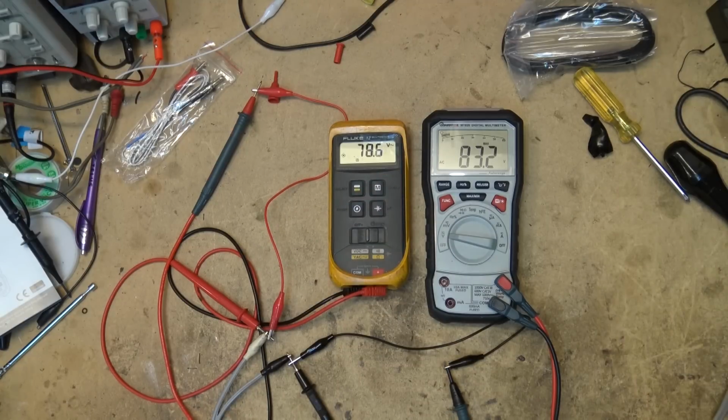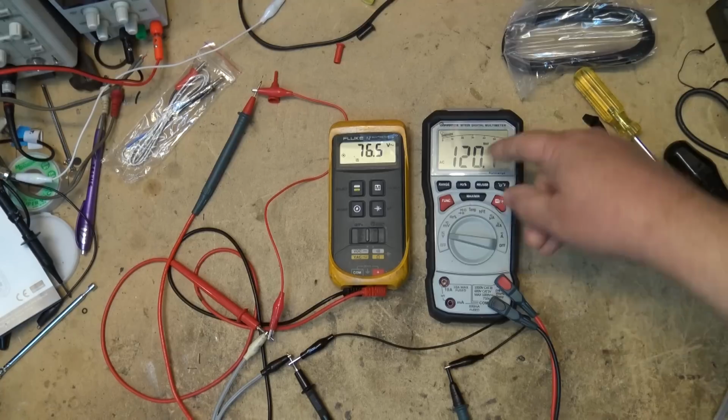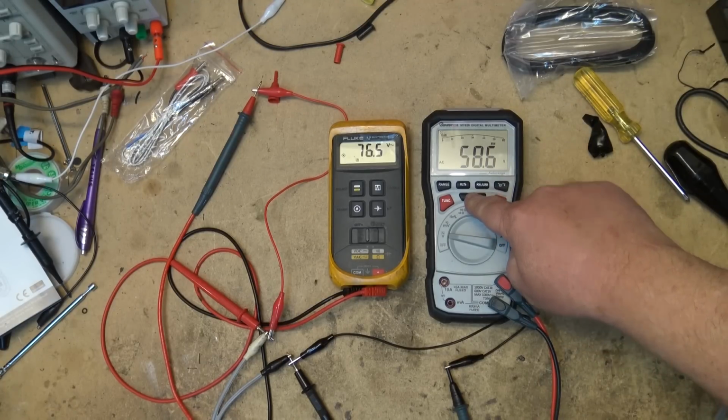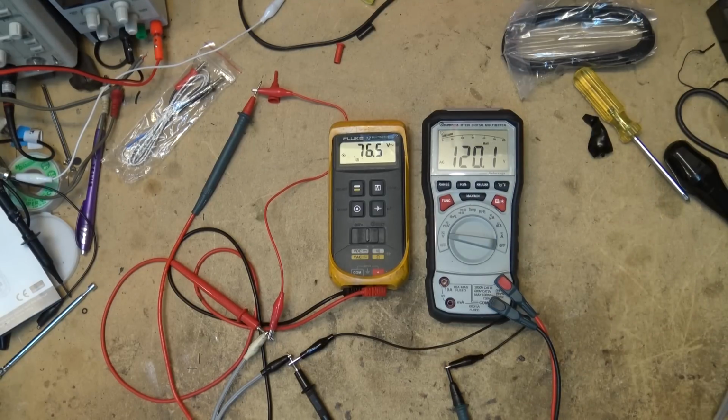This one here, if the voltage were to spike, it now has stored what the maximum was. It's telling me the minimum was 58, and the difference between the two was 61 volts. And if it were to go all the way up, I just cranked it to 150.